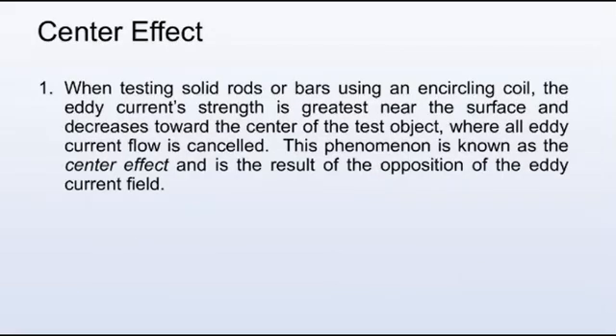When testing solid rods or bars using an encircling coil, the eddy current strength is greatest near the test object's outer surface and decreases toward the center of the test object.